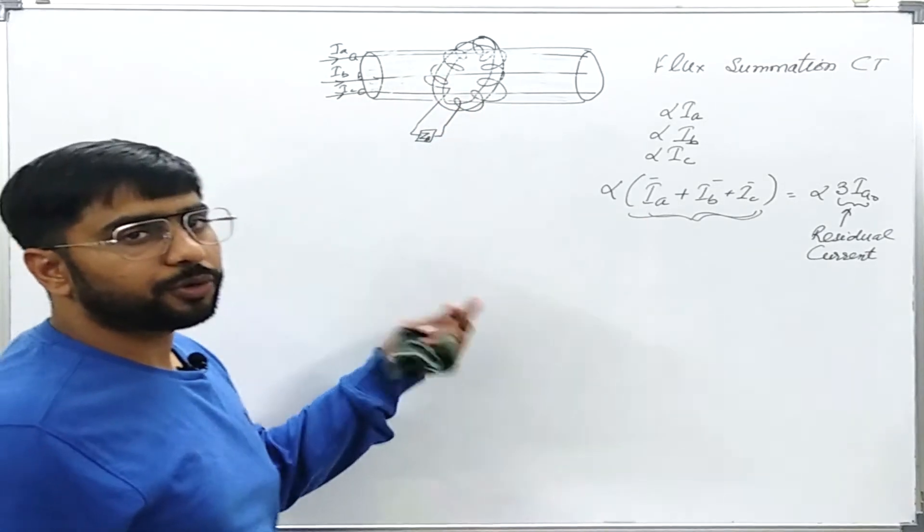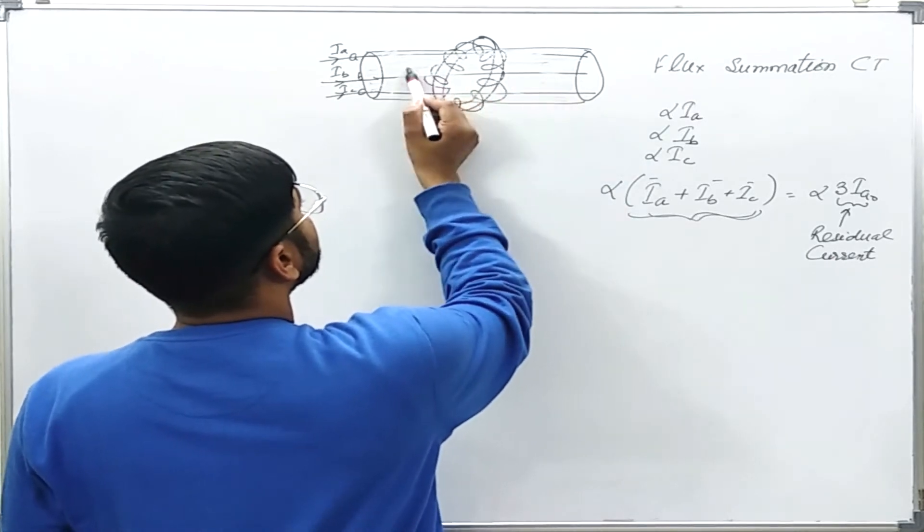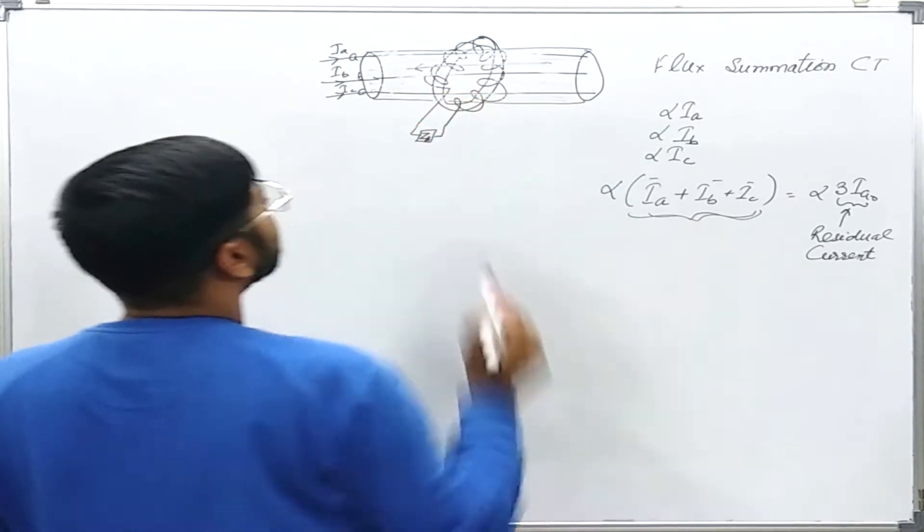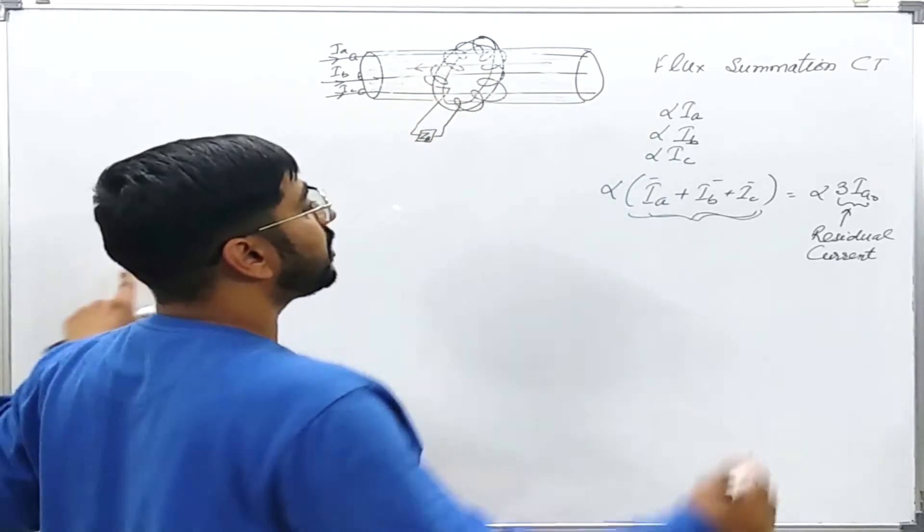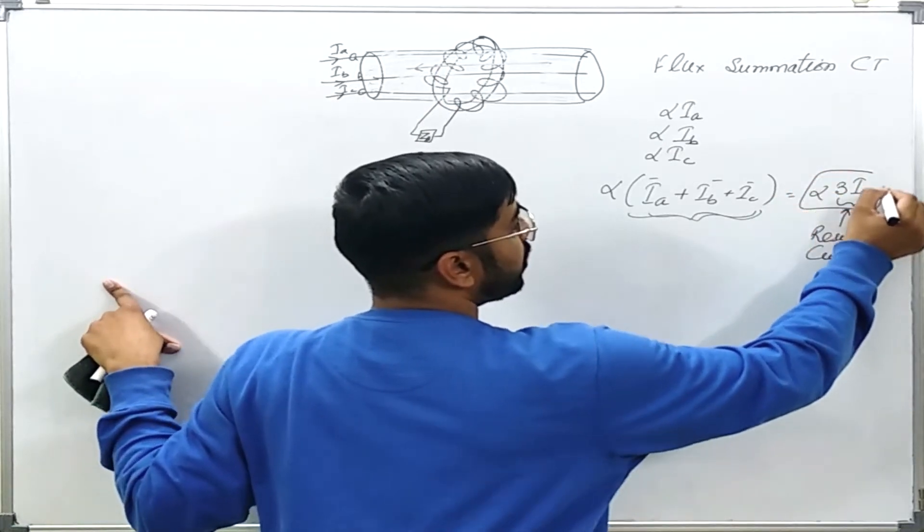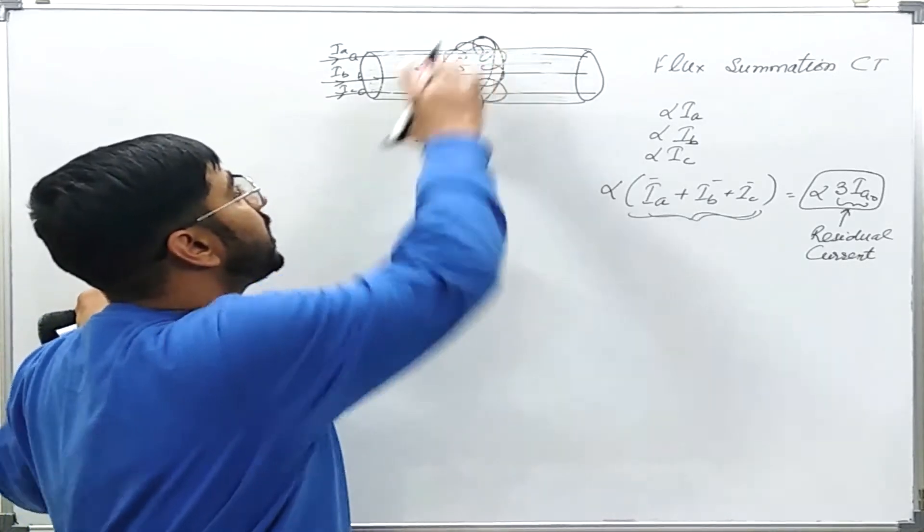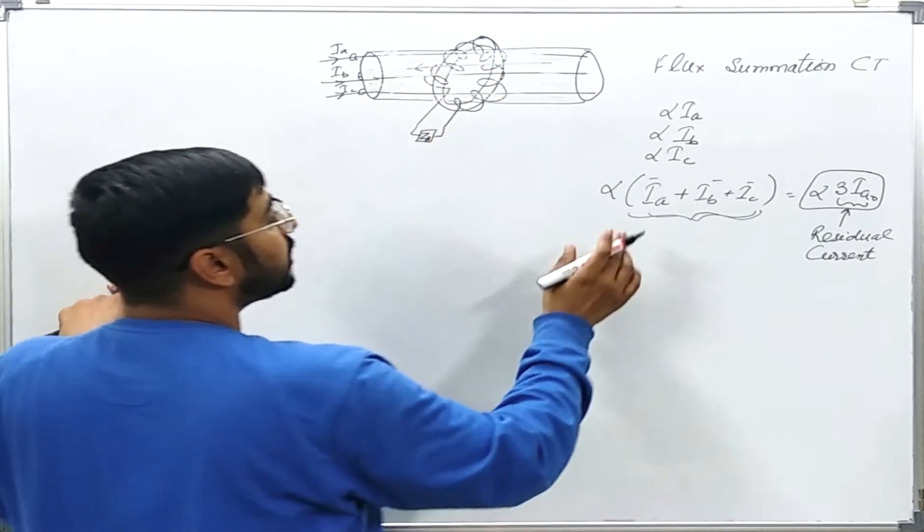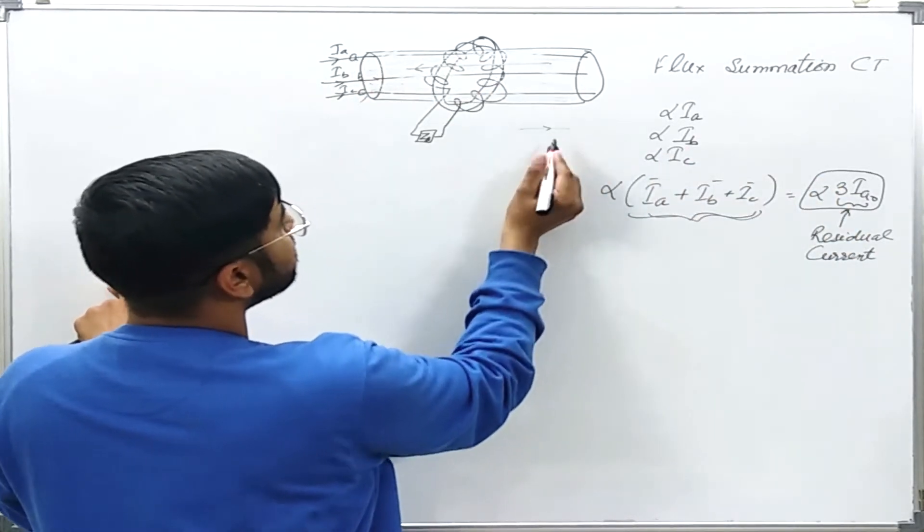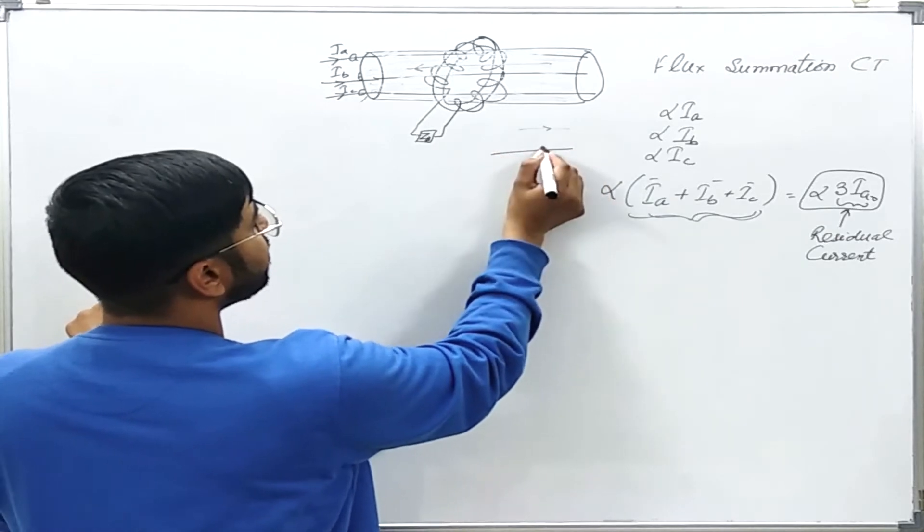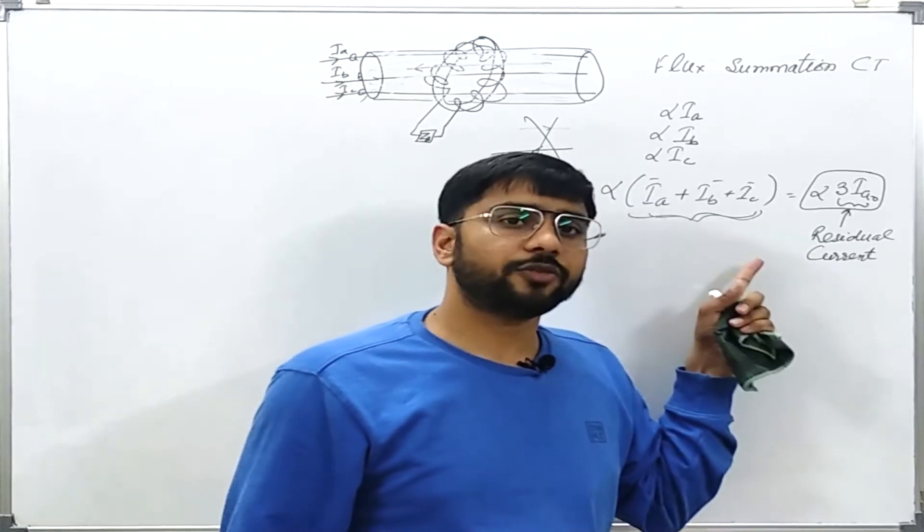This metallic sheath will be having some current, either due to the fault or due to some other scenario. And this current might be flowing in the opposite direction. On the similar principles of induction, this current will be similar to this 3IA0 only. The resultant flux in this CT now what will happen? It will get cancelled out. This 3IA0 because of the phase conductors in this direction and this 3IA0 because of the sheath current in this direction will get cancelled out. How to solve such kind of problem?